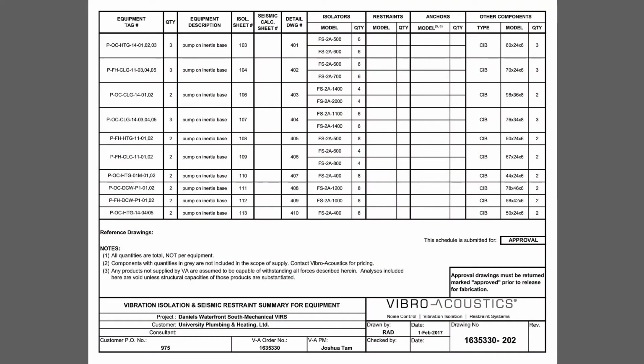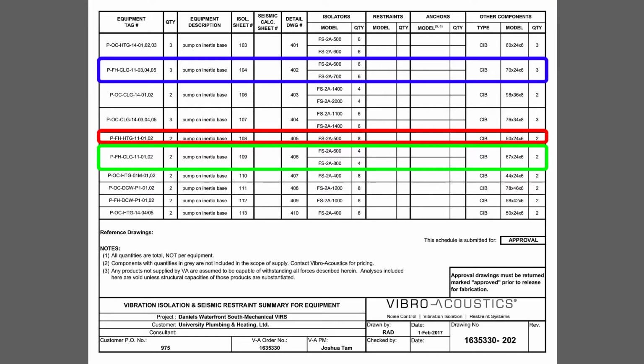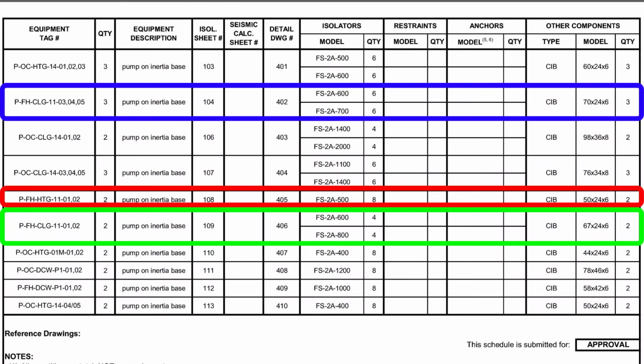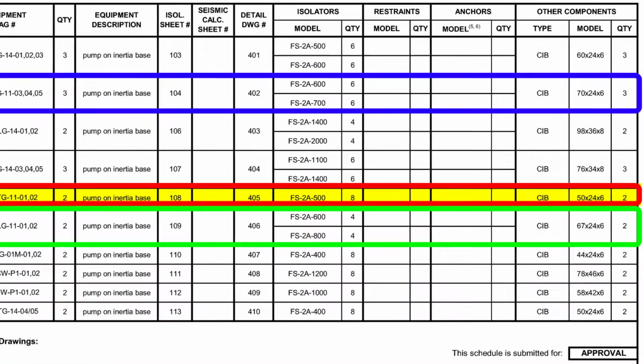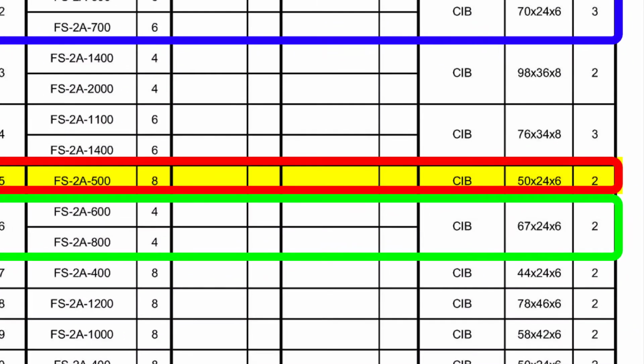Here is a summary page from our submittal showing the various pumps and the inertia bases and springs selected for each. These 3 lines show the 3 groups of pumps located in the mechanical penthouse. We'll take a look at each of these during our site visit, but first we'll look at products used for the heating water pumps, where we supplied concrete inertia bases, type CIB, that were 50 inches by 24 inches by 6 inches, as well as FS2A 500 isolators.